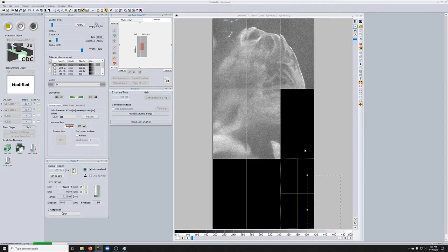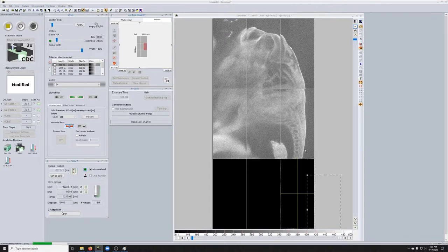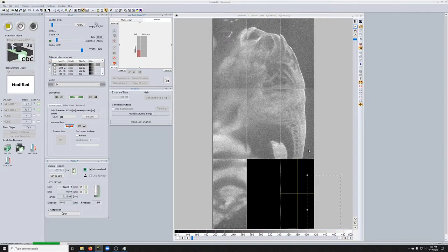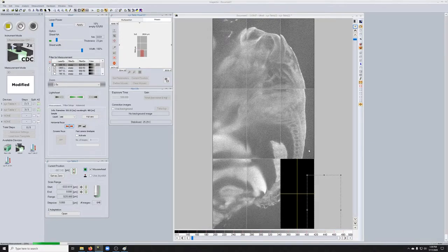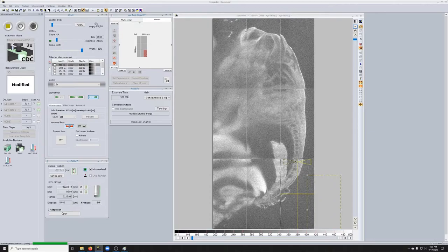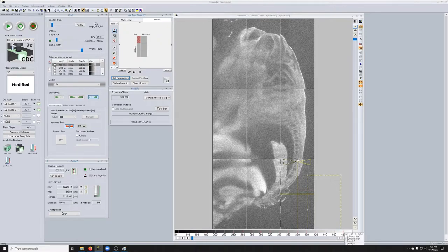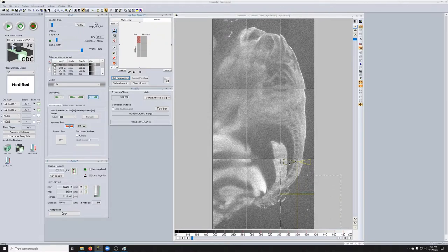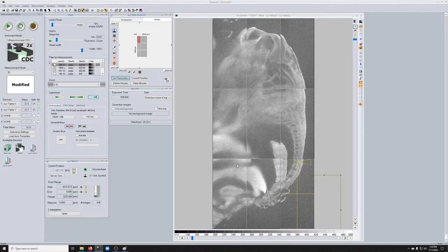Now, what we should see is that the thing that we're imaging in its entirety of the entirety of what we want to image should be in the field of view. And we should see some overlap. So you can see the overlap right here in the X dimension, which should be about 10%. And you can also see it in the Y dimension. It's a little bit trickier, but actually you can see it kind of here as well as here, where you can see this groove and then the groove there. So everything seems to be working well.